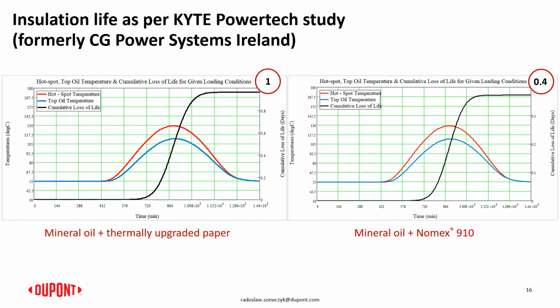It significantly reduced the aging of the insulation. The aging was reduced by 60% when the temperatures were kept the same. So this shows that the design could be significantly optimized, and either the actual power rating of the transformer could be reduced, or the temperatures could be increased, meaning the cooling system of the transformer could be reduced, in order to get closer to the more typical aging of the insulation system.